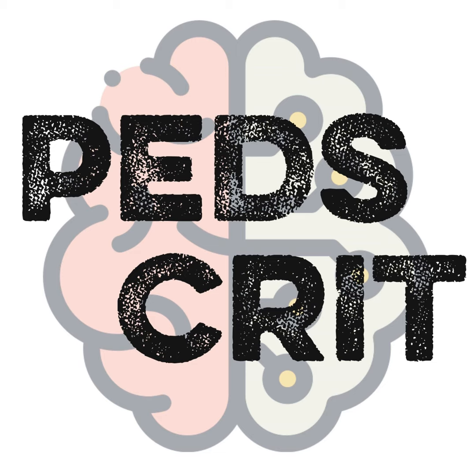The next one is pressure trigger. And in this case, it's the same idea. We have our set PEEP, which should be constant at the end of exhalation. And if that goes down, it means the patient has, in the ventilator's mind, sucked in enough air that it's dropped the pressure. And so therefore, the patient must be trying to breathe. Let me give a breath. That's a less sensitive trigger. So that's why we don't use it as much in peds, because it's hard for an infant, this 3-month-old that we just described with RSV, to suck in enough air to drop the pressure.